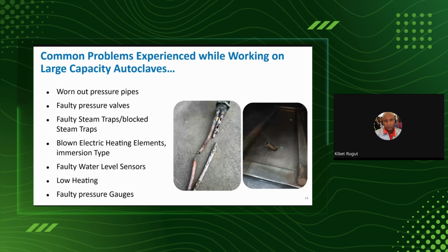So you realize that water sometimes is supposed to be well treated before entering the autoclave, but you may not eliminate all the chemical elements. So you might find that fluorine remains in the water and others. So you get the elements, since they heat very high, they can also have some chemical reactions and start wearing out the coating of the heating elements. So some of these are not strange when you see such a heating element being removed from your autoclave.